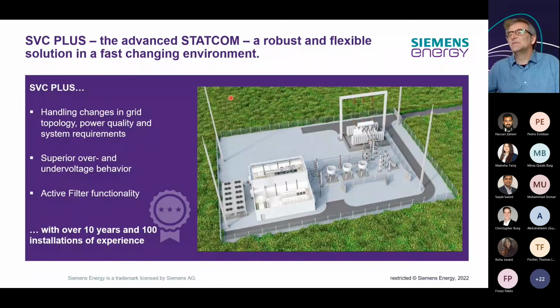So the SVC Plus, that is Siemens Energy's term for a STATCOM. You can say it here. A nice functionality, which is really worth mentioning, is what it provides by using these modern IGBTs: we have the active filter functionality. You can actively filter up to 4 different harmonics out of the system. It will automatically detect which harmonic is most affected, and it will optimize the parameters to filter those harmonics.